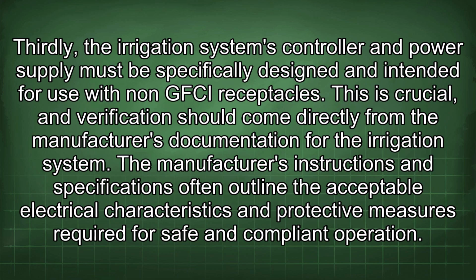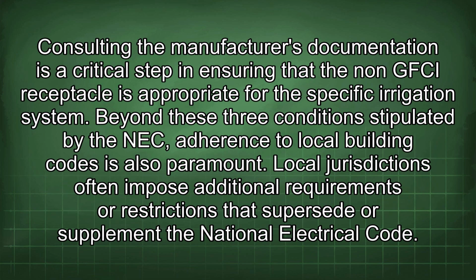Thirdly, the irrigation system's controller and power supply must be specifically designed and intended for use with non-GFCI receptacles. This is crucial, and verification should come directly from the manufacturer's documentation for the irrigation system. The manufacturer's instructions and specifications often outline the acceptable electrical characteristics and protective measures required for safe and compliant operation. Consulting the manufacturer's documentation is a critical step in ensuring that the non-GFCI receptacle is appropriate for the specific irrigation system.